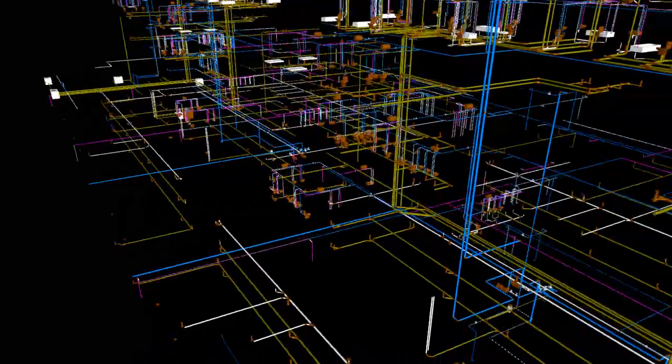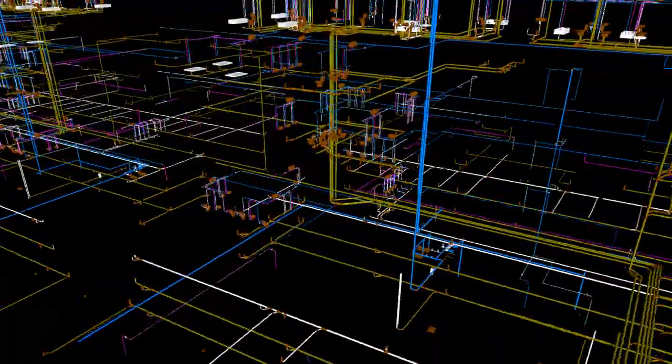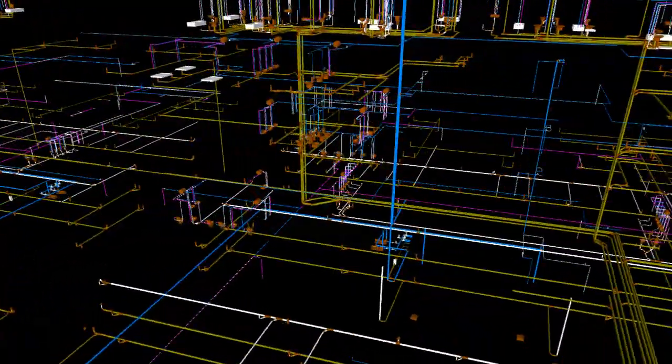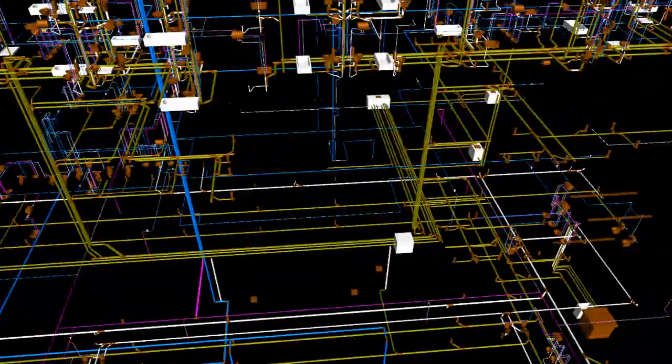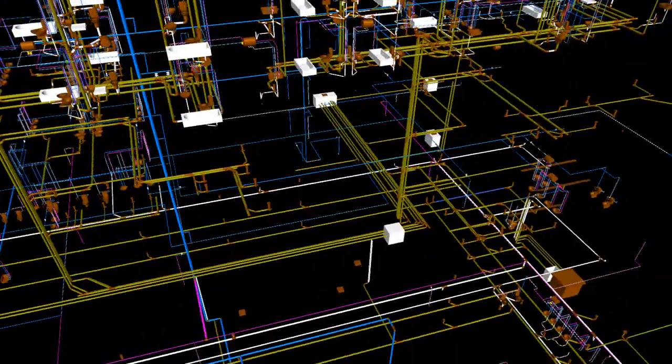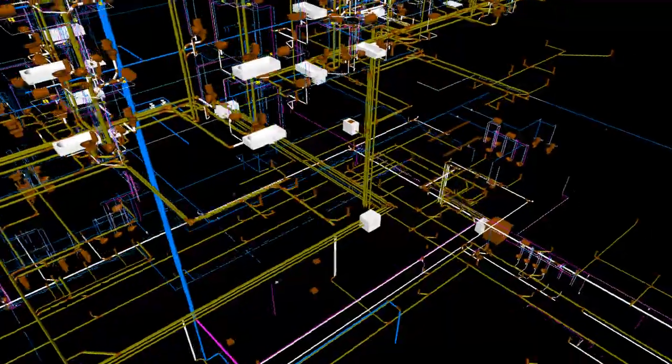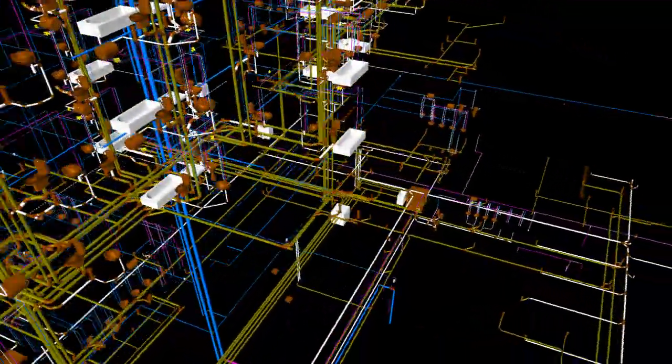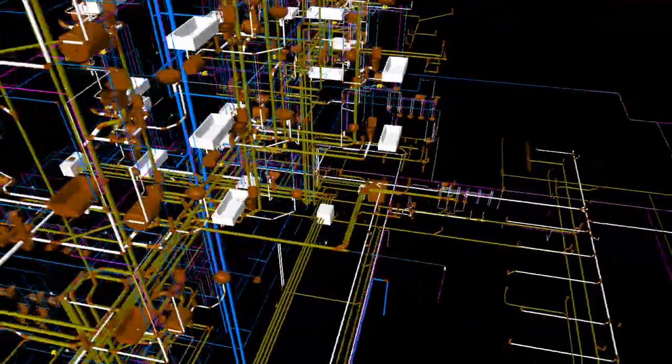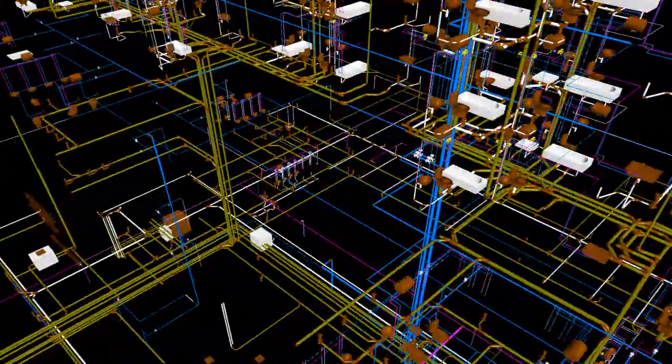Condensate drain from AC units shall be connected via U-trap to the nearest floor drain or waste stack. Since the domestic water storage tank is proposed to be combined with irrigation water storage requirements, the condensate drain from FAHUs shall not be connected to water storage tank.